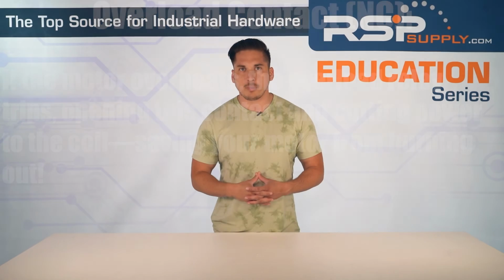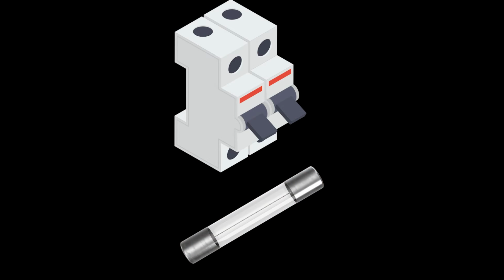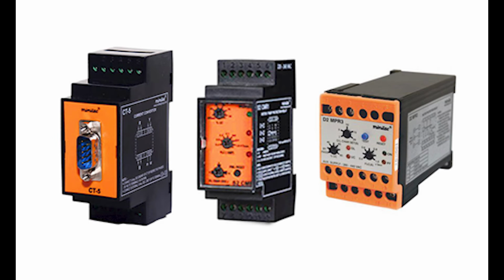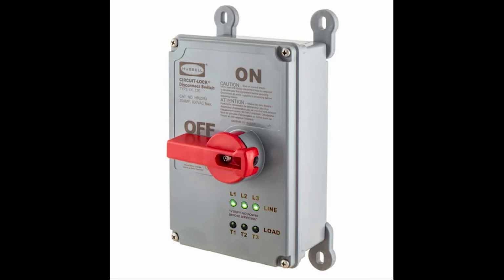Now let's talk electrical protection. So motors are expensive, so we protect them. Here's how. Circuit breakers and fuses, obviously. These are going to stop catastrophic failures like short circuits by cutting power fast. Motor protection relays. These smart devices detect problems like phase loss, unbalanced loads or locked rotors before damage happens. Disconnect switches. So if you need to work on the motor safely, a disconnect switch makes sure there's no accidental power-ups. So some selection criteria for when you're selecting contactors.